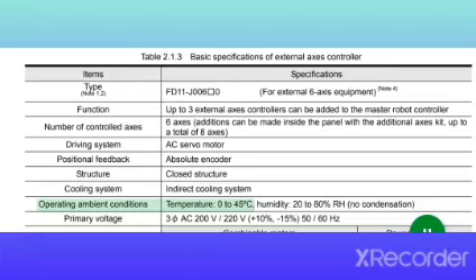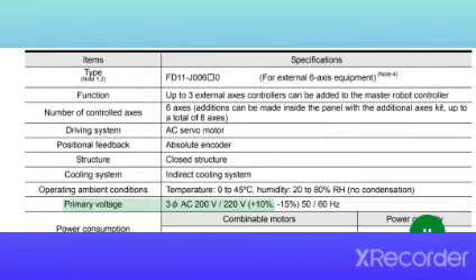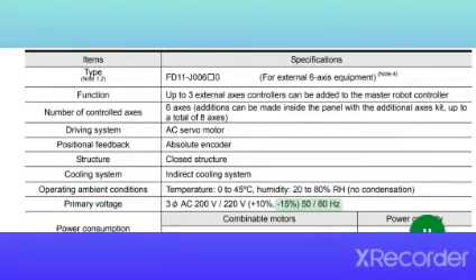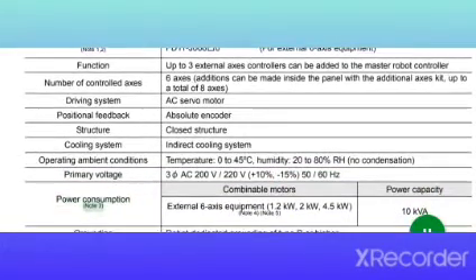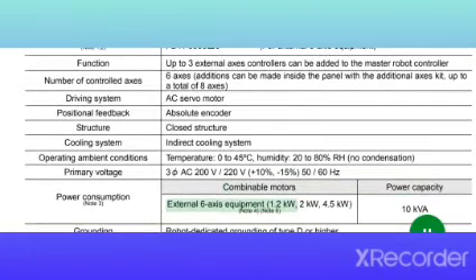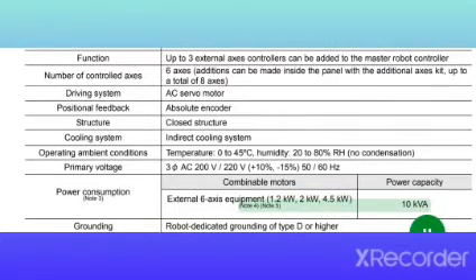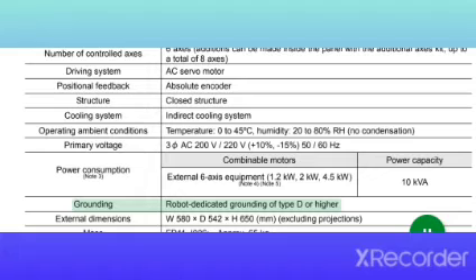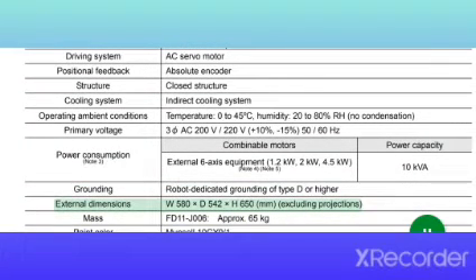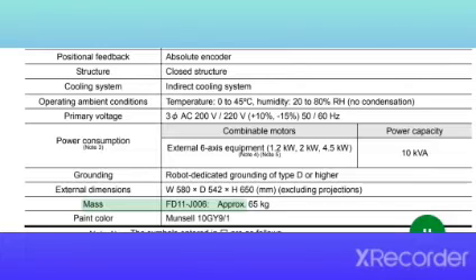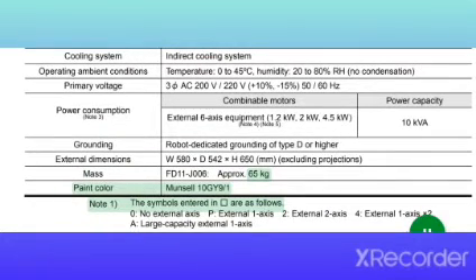Operating ambient conditions: temperature 0 to 45 C, humidity 20 to 80%, no condensation. Primary voltage: 3-phase AC 200 V/220 V, plus 10%, minus 15%, 50/60 Hz. Power consumption, Note 3. Combinable motors: external 6-axis equipment, 1.2 kilowatt, 2 kilowatts, 4.5 kilowatt. Grounding: dedicated grounding of type D or higher. External dimensions: W580 x D542 x H650 mm excluding projections. Mass: FD11-J006 approx. 65 kilograms. Paint color: Munsell 10GY9/1.